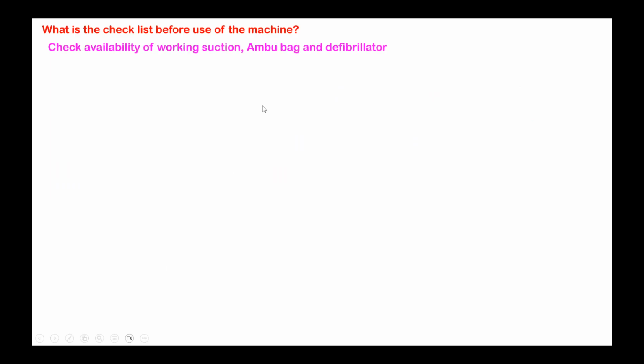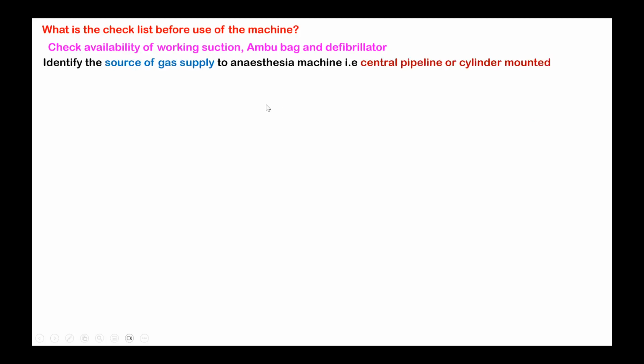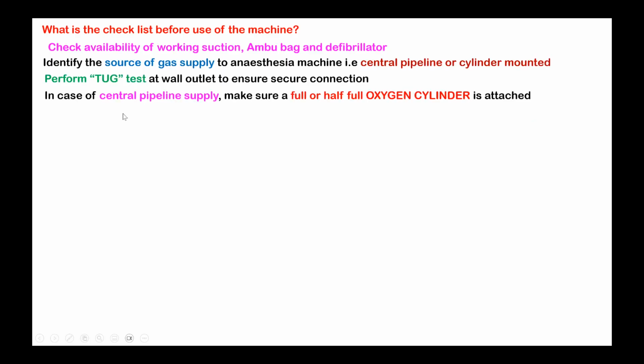Checklist before use of a machine. What are all the things you should check? Can you enumerate that? First and foremost, check for availability of suction, Ambu bag, and defibrillator in the theater. Okay. Then identify the source of gas supply, whether it is coming from a central pipeline or a cylinder attached to the machine. Perform a tug test at the wall outlet. In case of central pipeline supply, see whether you have a spare oxygen cylinder attached to the machine or not. And check flow of oxygen from the auxiliary flow meter.